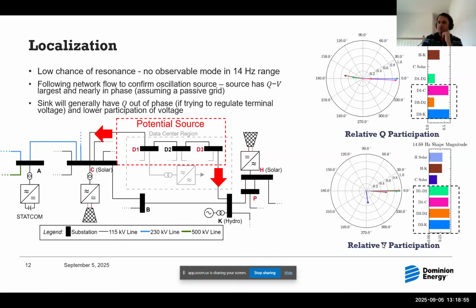What you'll see is that the data center bus has the maximum voltage magnitude participation in this oscillation, and also the maximum reactive power. Furthermore, the reactive power and voltage magnitude are nearly in phase, which gives a clue that this must be feeding the oscillation.